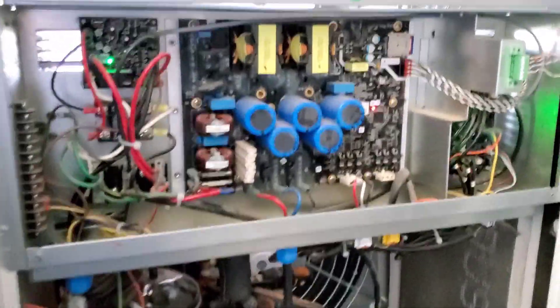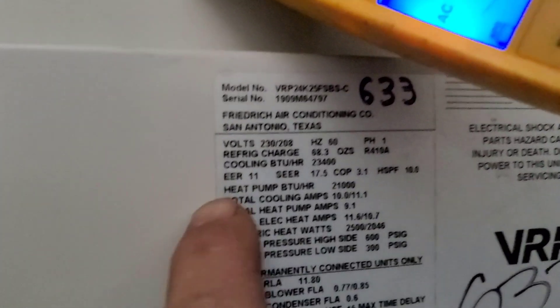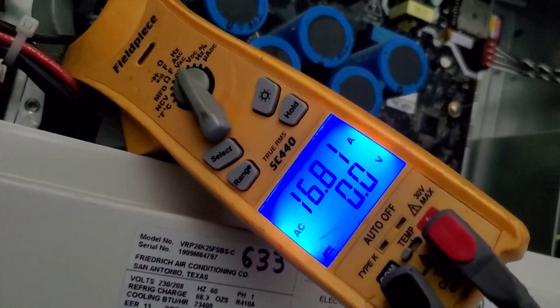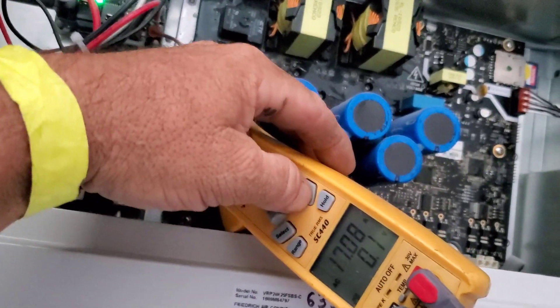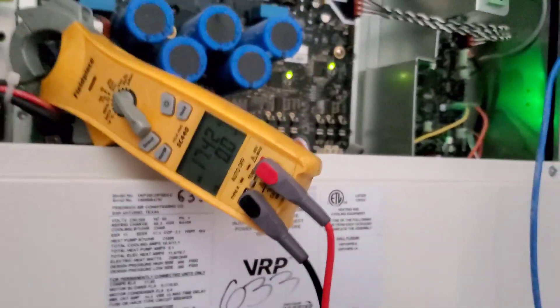A lot of times when they send us a compressor, Friedrich will send us a circuit board with it — they just think when these things get over-amped, the board's done too. I'm on another Friedrich unit now — 16 amps total, 11.1 amps cooling. For 208 volts, right now 16.5 amps — that's only what's going into the inverter board, so it's 5 amps over. 17 amps — the breaker is tripping on this thing. 17.3 amps. I'm going to hook the pressure gauge up. I think I see the problem on this one — remember how there's daylight up where it draws air in? It's closed. There's a piece of solid metal right there blocking the inlet.